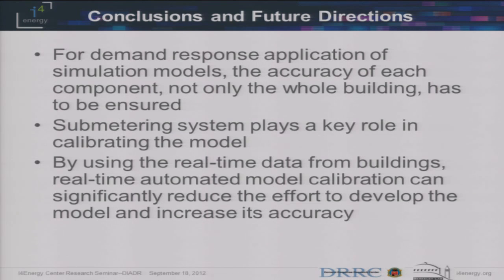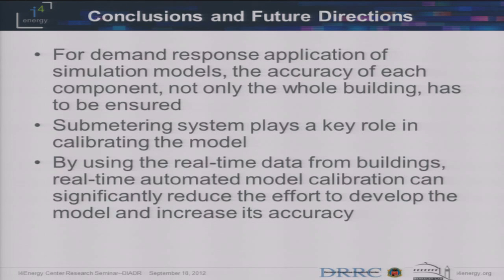For the demand response application of simulation models, accuracy of each component — not just the whole building — must be ensured. That is the key point to improving simulation model accuracy. Secondly, the submetering system plays a key role in calibrating the model — through the data points from the submetering system, we can identify where the error is. Thirdly, by using real-time data from the building, we can perform real-time automated model calibration, which reduces the effort to develop the model while increasing model accuracy.